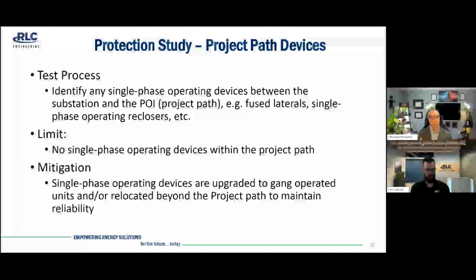Project path devices: this is looking for any single phase operating devices between the substation and the point of interconnection. So that's the project path. We'd be looking for fused laterals or fuses within the project path, single phase operating reclosers, etc. The criteria is usually that those need to be removed and replaced with gang operated units or relocated beyond the project path.